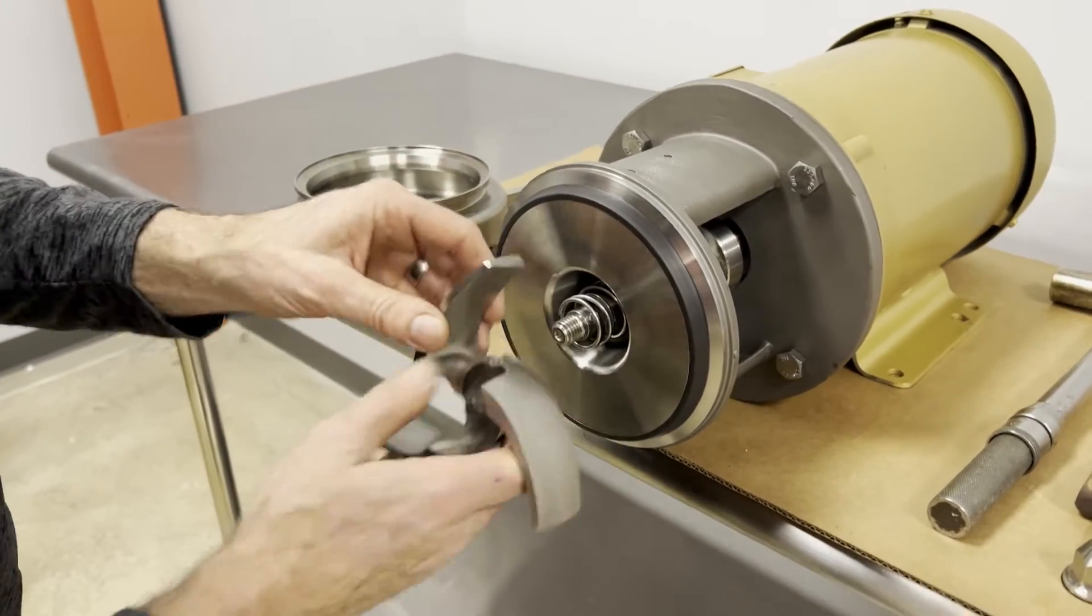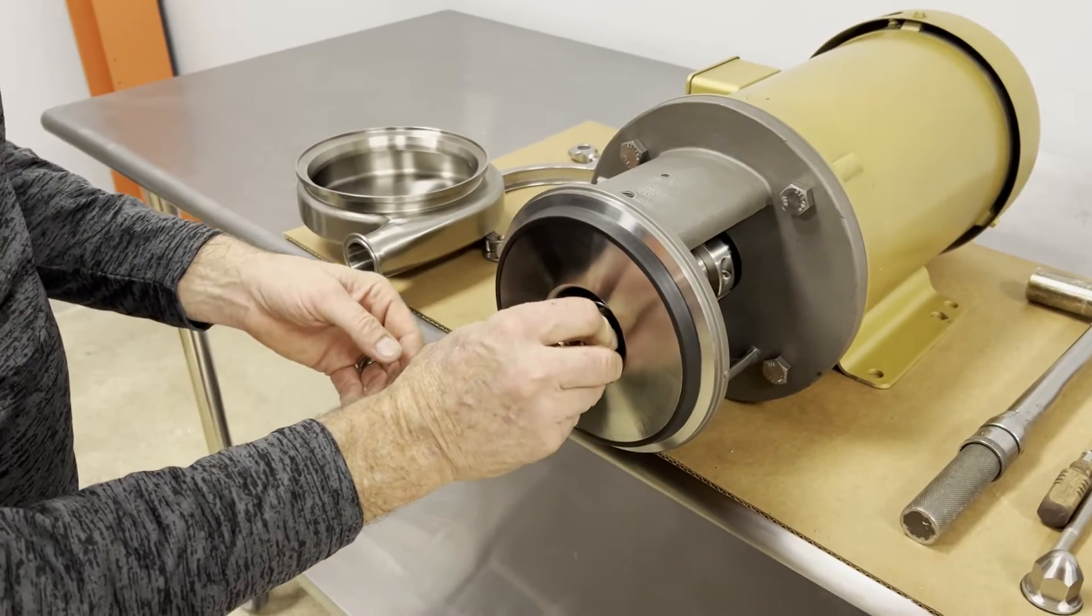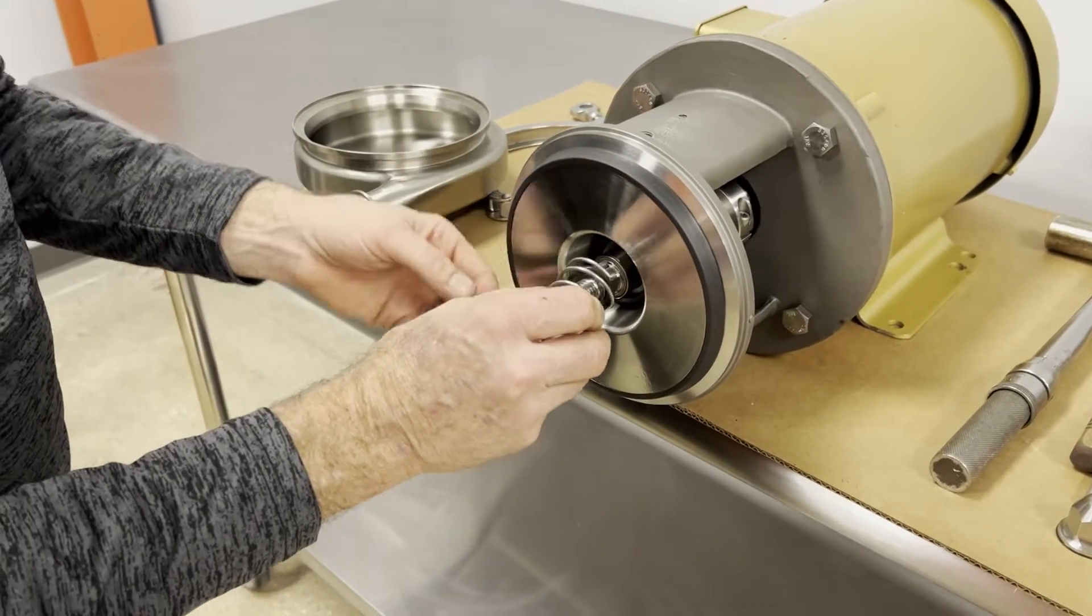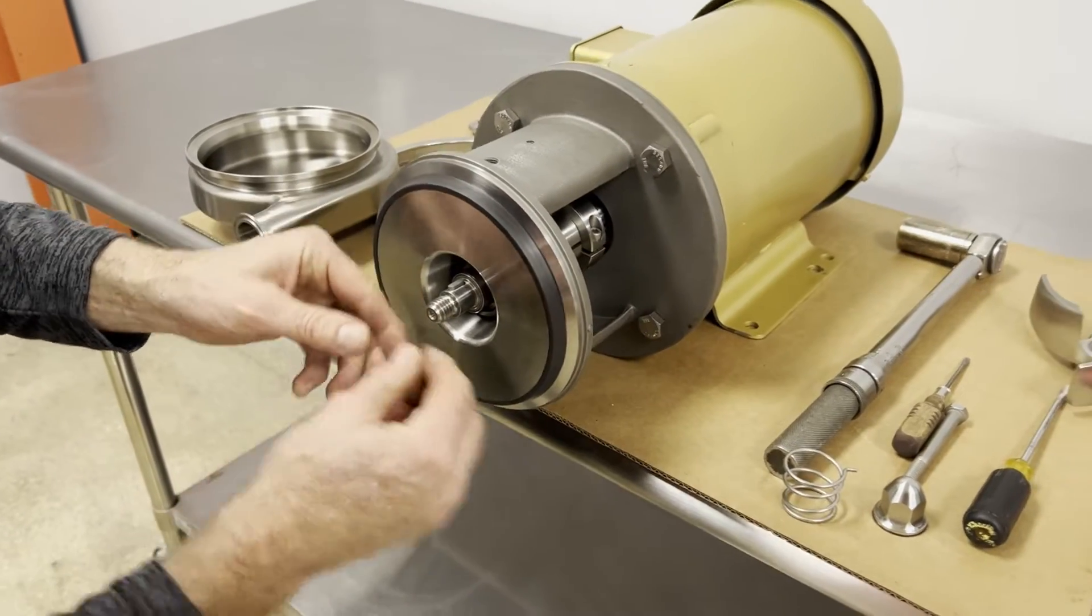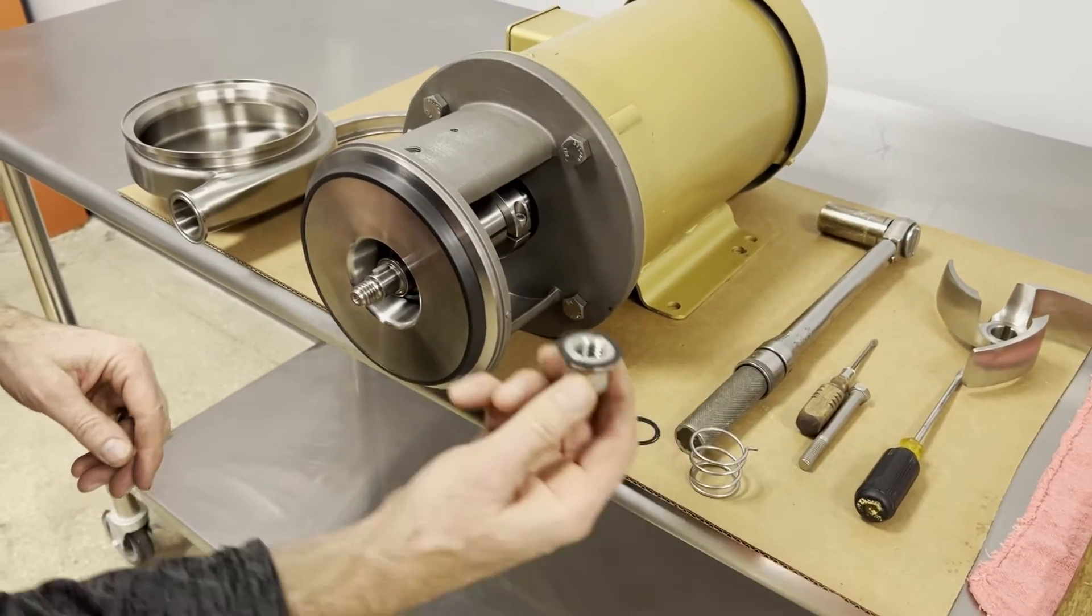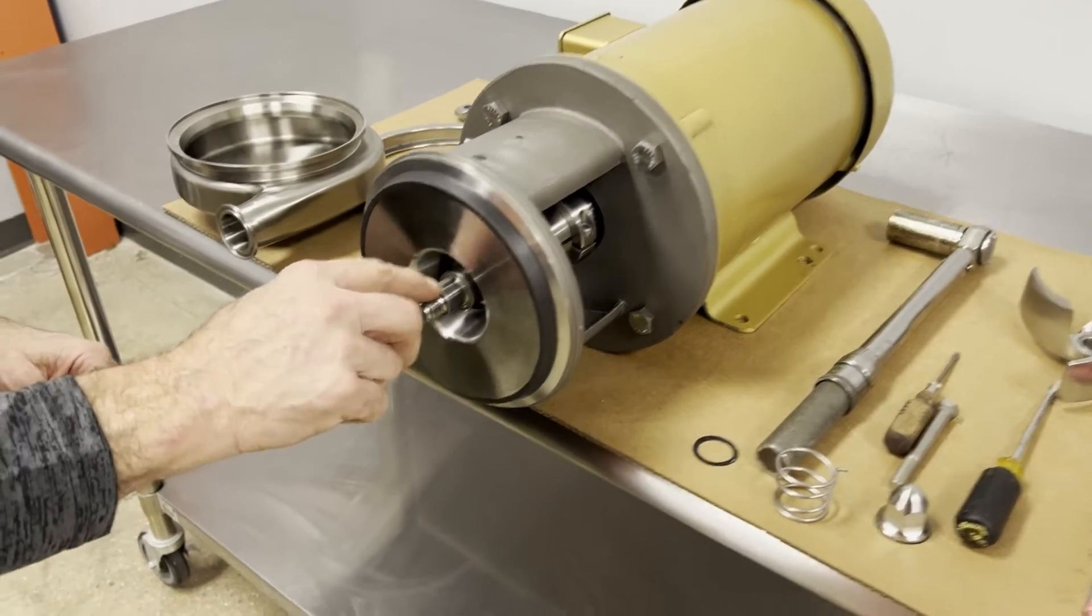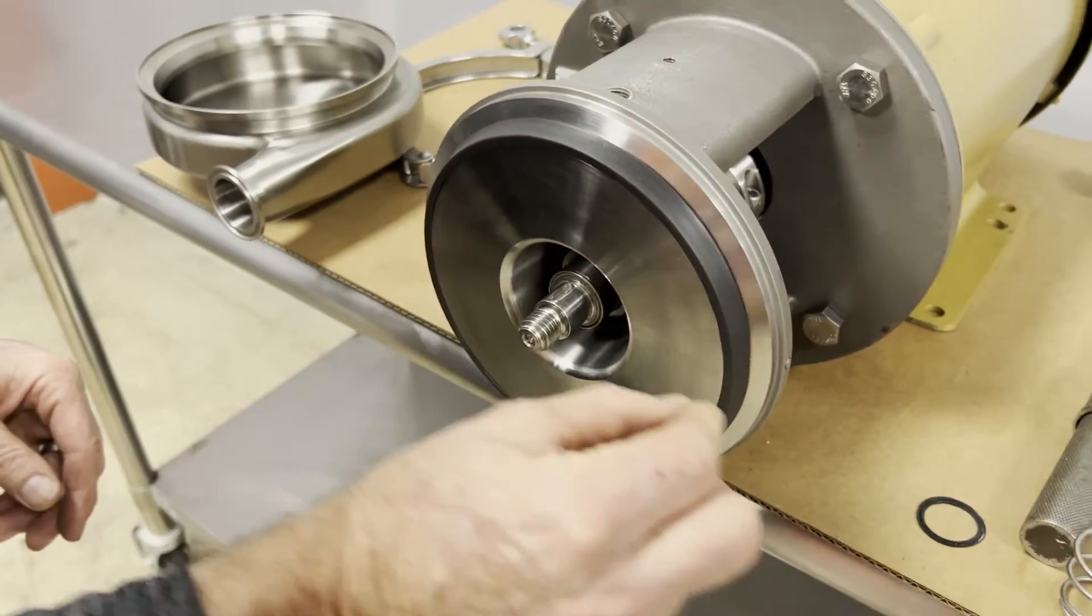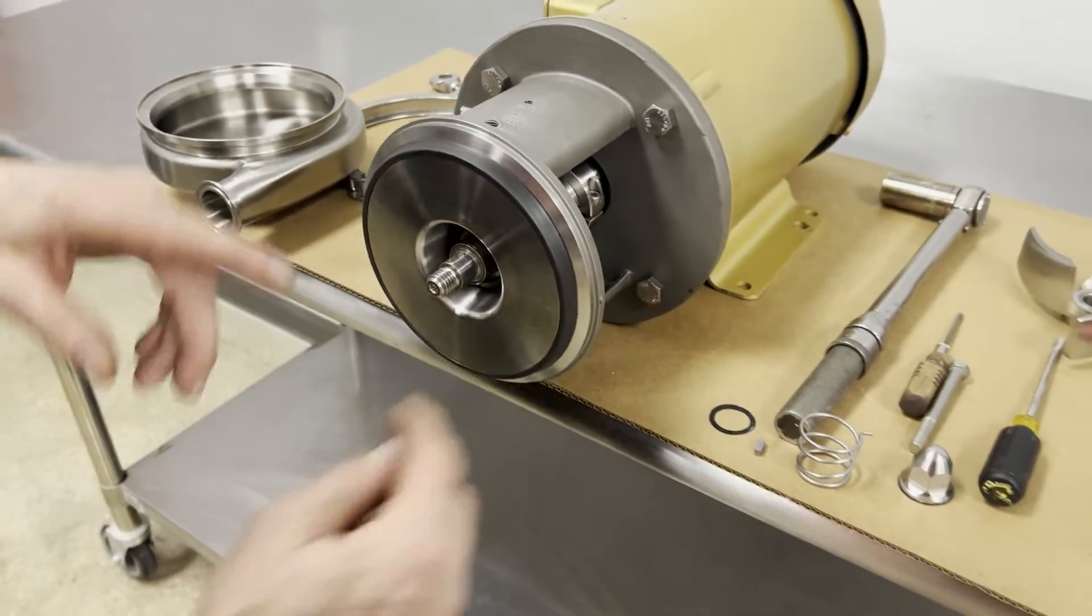Carefully take off the impeller, the spring from the seal. There's a gasket on the stub shaft, there's also a gasket on the impeller nut, and then there's a key in the shaft that you're going to want to remove and set that aside.